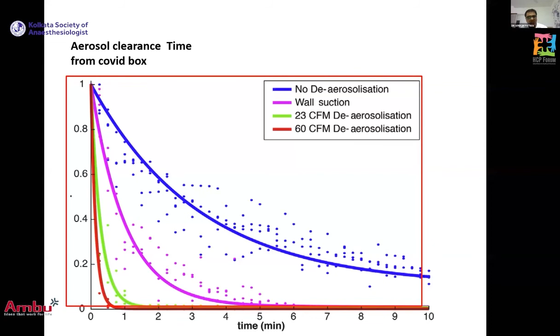And if you keep 60 CFM, cubic feet per minute, de-aerosolization by that power of suction, then hardly half a minute, 30 seconds, is required to clear all the aerosol. So this is how you can make practical use of the COVID box in your clinical scenario.